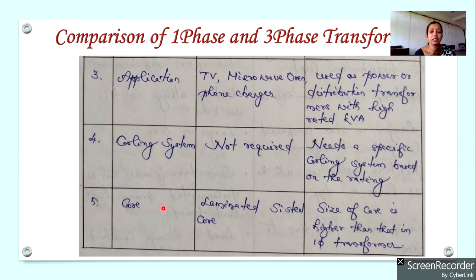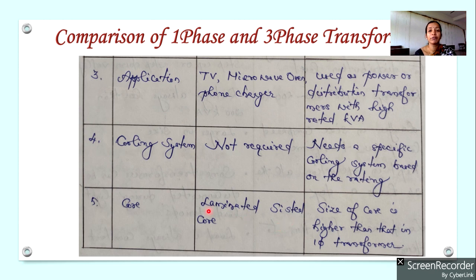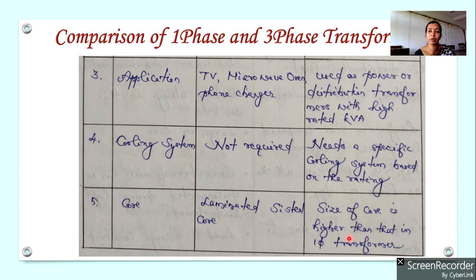Regarding the core: single phase transformers use a laminated silicon steel core. The core is laminated to reduce eddy current loss, and silicon steel is used to reduce hysteresis loss. Three phase transformers also use laminated silicon steel core, but the size of the core will be larger than that used for a single phase transformer.